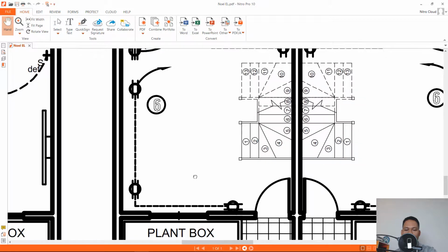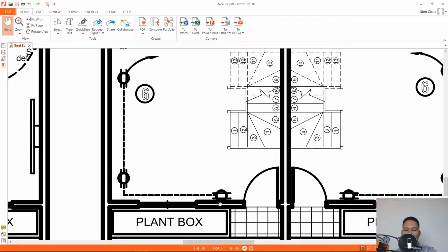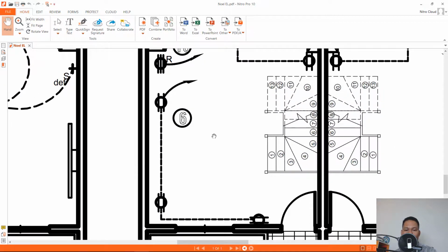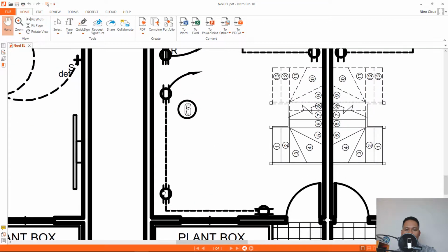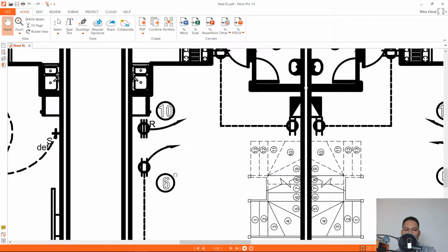Remember, guys, the outlets should be 40 centimeters from the finished floor line, so just follow this plan. As you can see, the outlet here near the door opening, you have one, and also near the corner at the side of the wall, and you have also one here. So that's circuit number six.